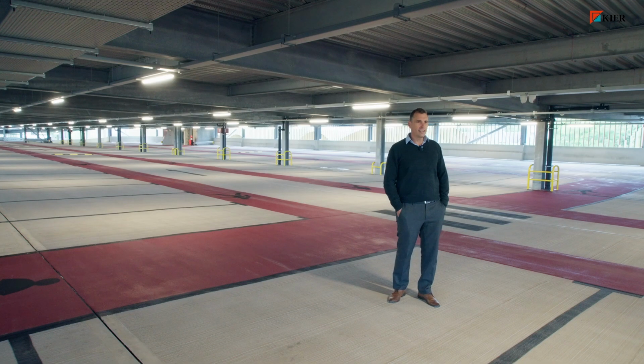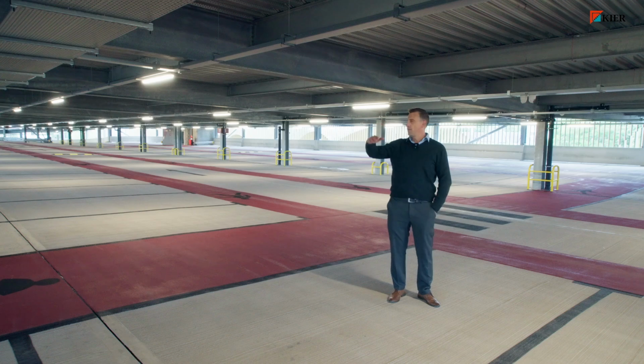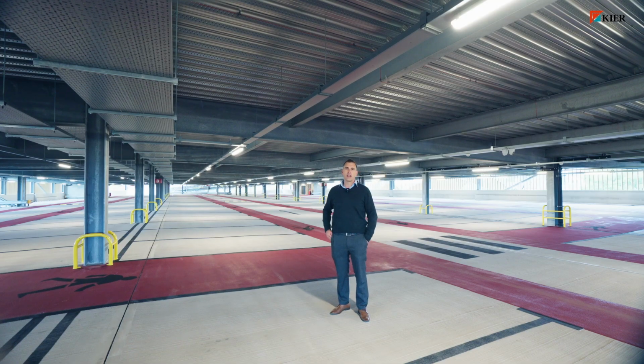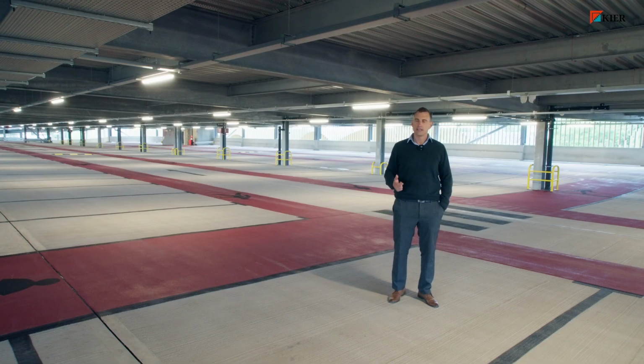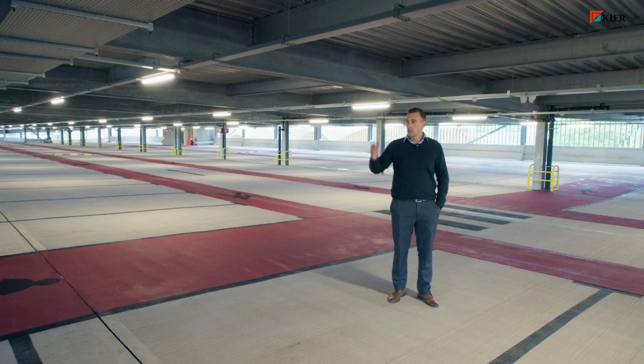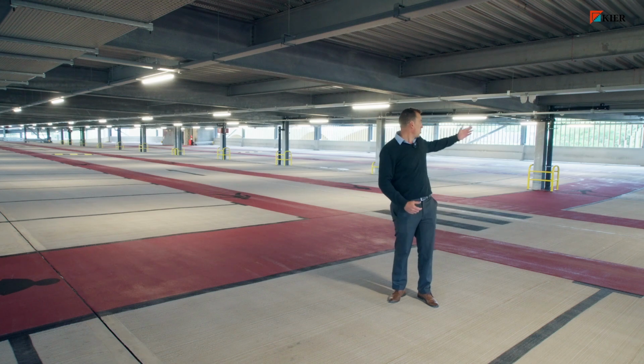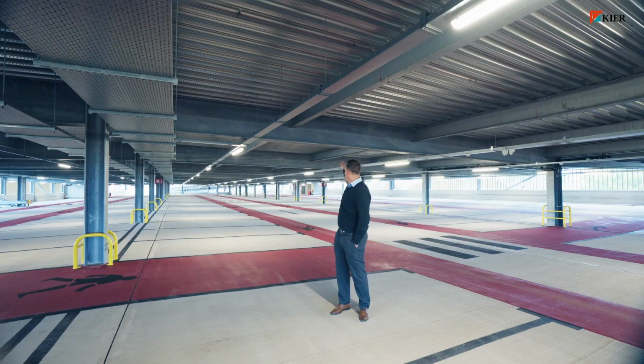With regards to lighting control, every floor is split into quarters, and each quarter has 50% of the light fittings on a timer, and the other 50% are on a PIR. So at any given time, from the set parameters of 6 a.m. in the morning till 10 p.m. at night, 50% of the lights will be on, unless the rest are activated via a PIR. That is the case at quarter 1, quarter 2, quarter 3, quarter 4.